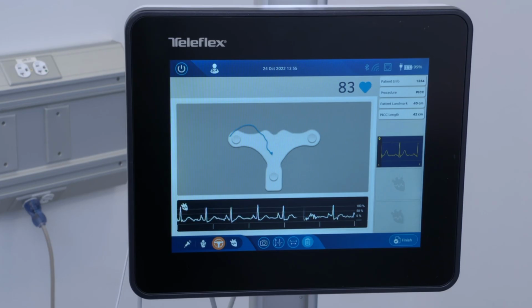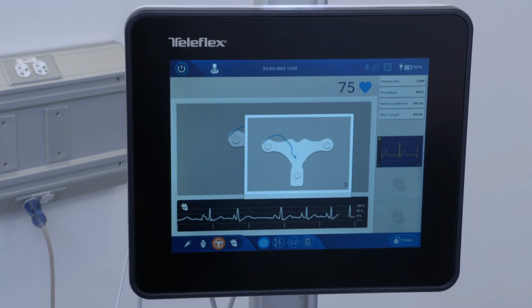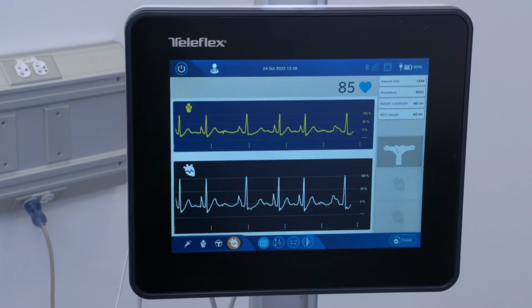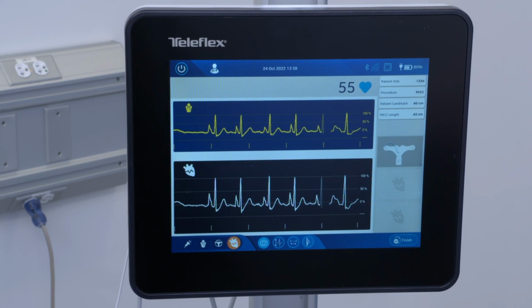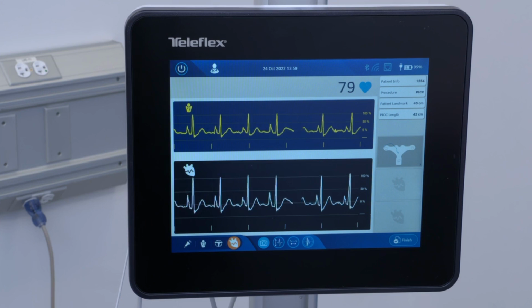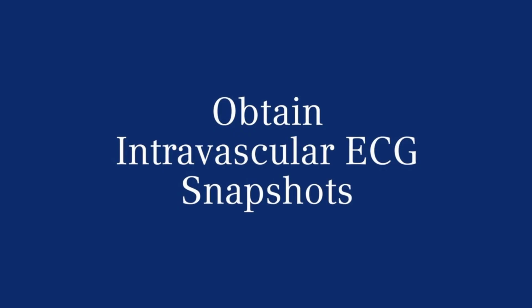The user can take an optional snapshot of the blue tip tracker technology line, showing that it is descending towards the SVC. When the user takes an optional snapshot of the tip tracker technology line, the device will automatically switch to intravascular ECG mode. The user can also move into intravascular ECG mode by selecting the heart icon on the bottom left corner of the screen using the remote.